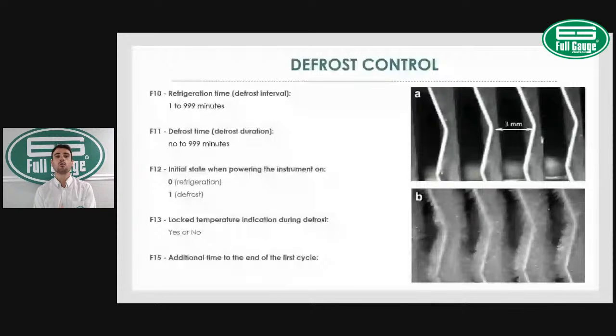So that's the reason why sometimes you set the controller to start under defrost. Let's say we had 4 hours of refrigeration, then a power failure. Whenever power comes back on, the system performs a defrost, ensuring that the coil is free of ice and good to go, and we can have our normal refrigeration cycle after that. So that's the purpose of F12, the initial state when powering the instrument on. Any questions about that? Please feel free to ask.